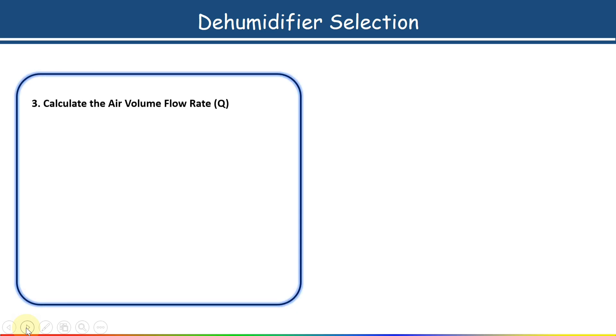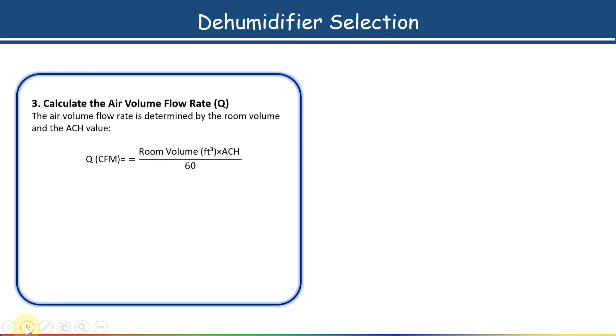The third step is to calculate the air volume flow rate. The formula is: Q = (Room Volume in cubic feet × ACH) / 60.